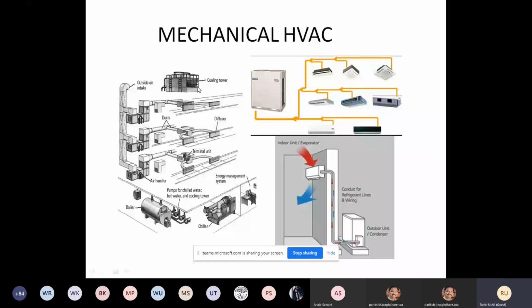The chiller produces chilled water. When it is producing chilled water, it has to take away the heat from the building environment, and it does that by way of a cooling tower and a condenser water system. So the heat gets carried to the cooling tower. There are fans on top of the cooling tower. The water falls through baffles in the cooling tower, and as it falls, the heat is picked up by the atmosphere. There's a bit of drip, some evaporation, and then the cool water comes back to the chiller.